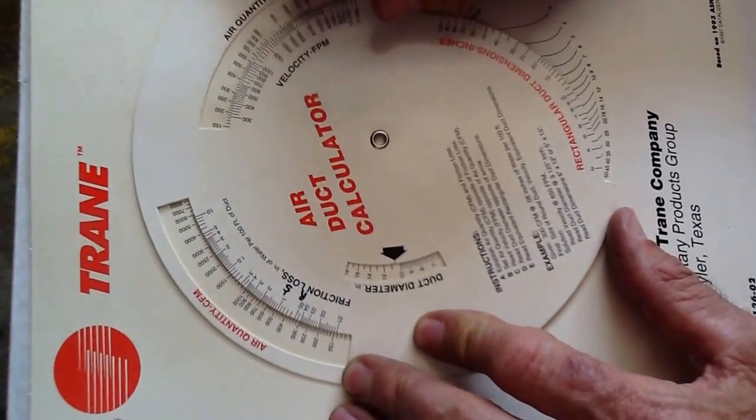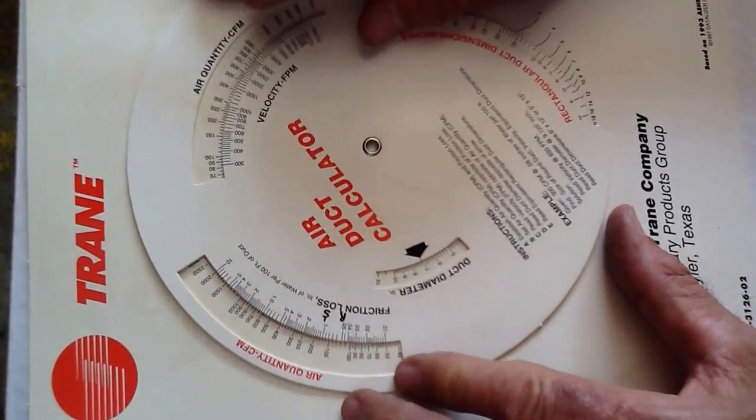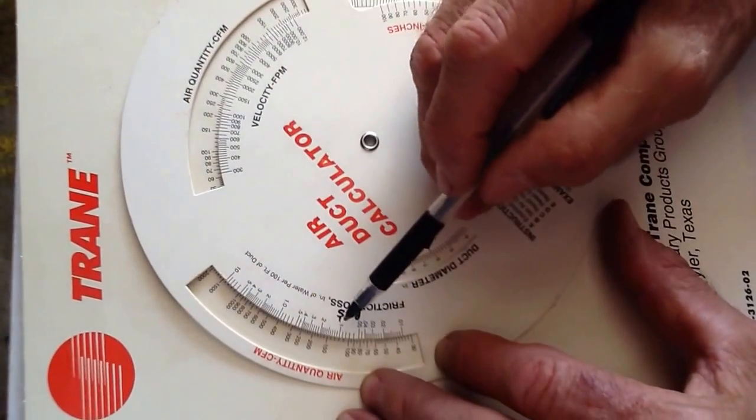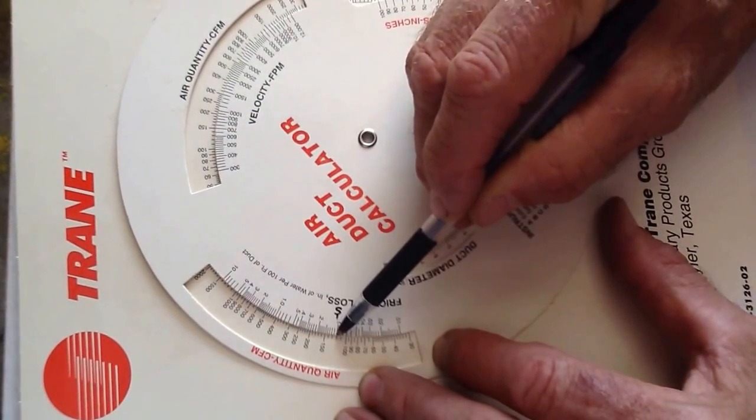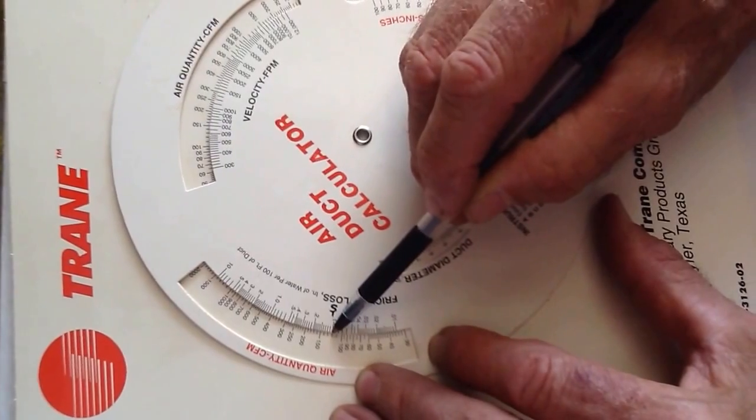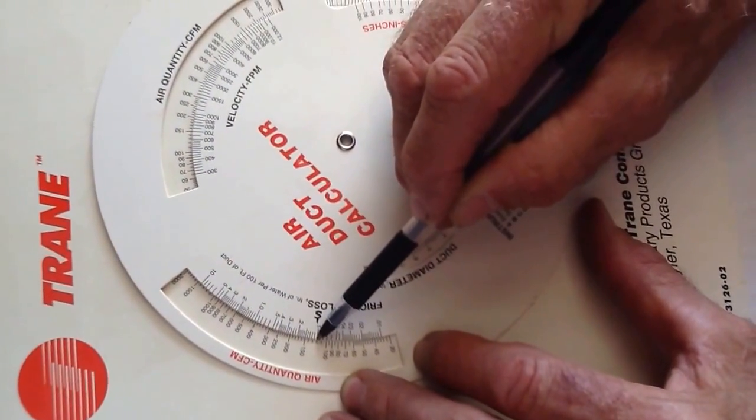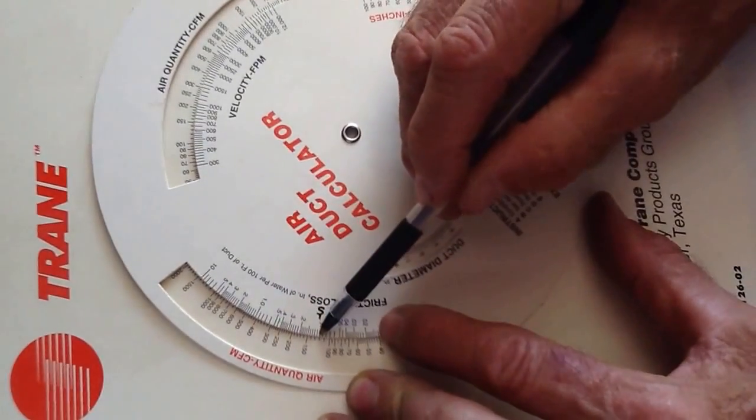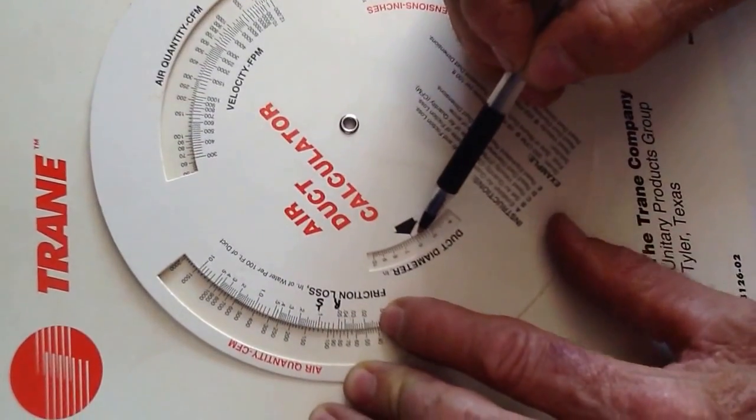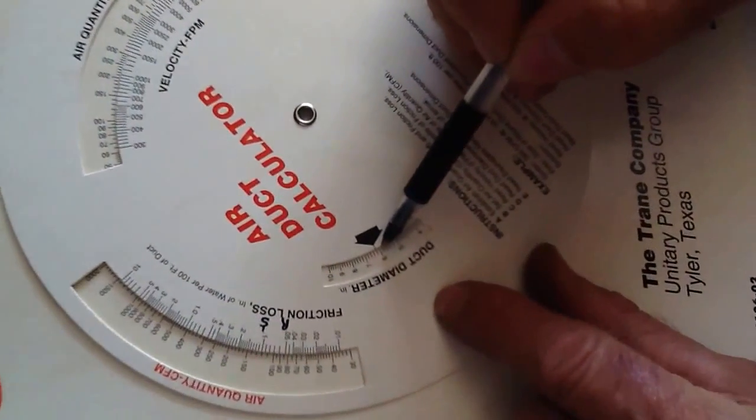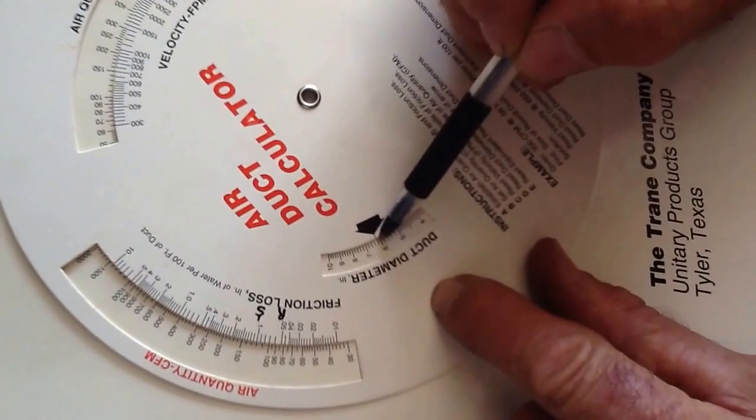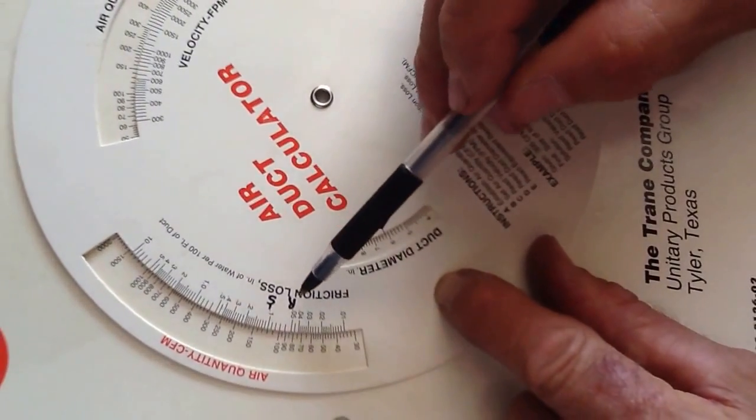At 120 square feet, one CFM per square foot, that's right there - 120. You look at this right here, you see the six inch, you automatically go up. They don't make a six and a quarter, you go to the seven inch. So that particular bedroom would require a seven inch flex.